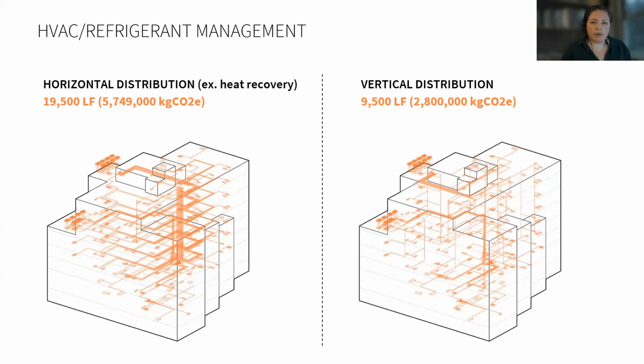Two other critical quality control concepts are to provide access panels at connections and ensure that the owner is provided with a documented record of the amount of refrigerant in each line based on as-built calculations of refrigerant lengths and the charging amount during final testing and commissioning.